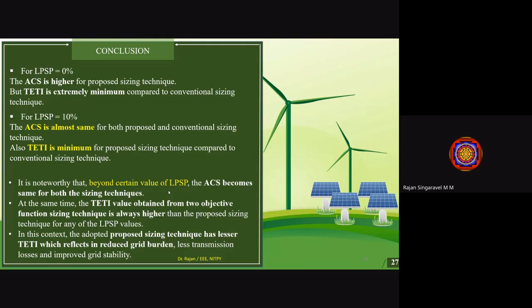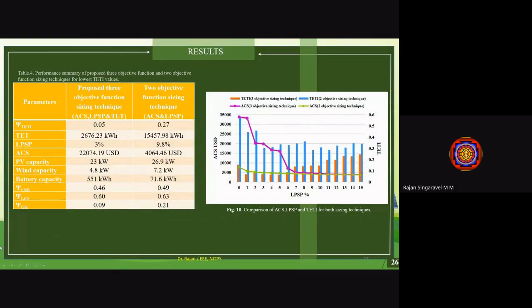Now, by the adopted procedure, you can see here the grid interaction index, GII. It is just 0.09 because the system merely interacts with the grid. Most of the time it has its own sustainable power generation. It hardly interacts with the grid, hardly imports power from the grid, hardly exports power to the grid. So the impact of this building on the grid is negligible.